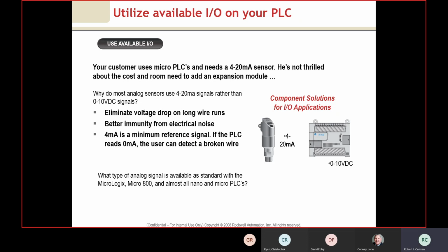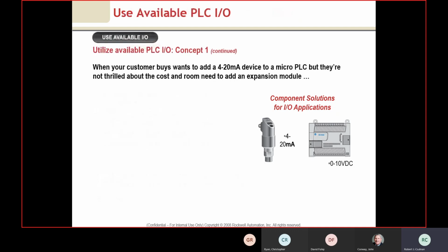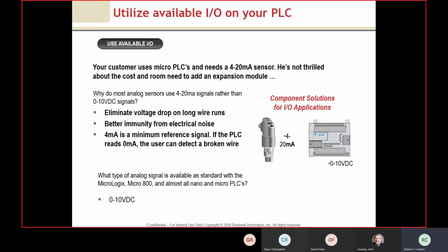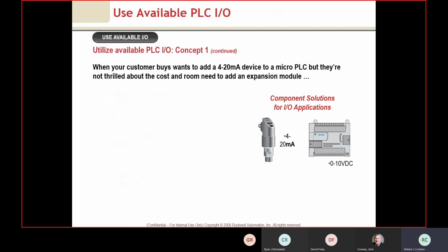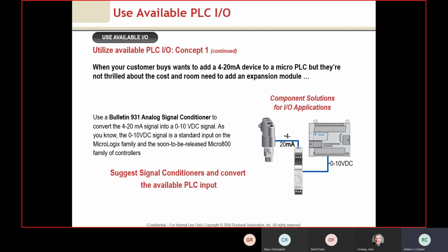There are some other things that happen with the signal converter. We now eliminate any voltage drop that we typically would find. We're going to get some better immunity in the unit itself. And we could also detect a broken wire because we're at 0 milliamps. So that's the way to convert. If we take a look at the unit here, the family of those devices is Bulletin 931, and in this case, it converts from 4 to 20 milliamps to 0 to 10.